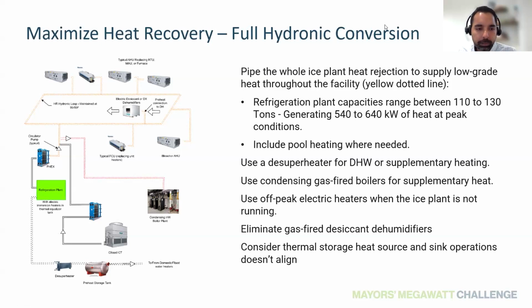Conceptually it's pretty simple: you have heat available from your ice plant that is generally being rejected to the outside through a cooling tower. When we try to decarbonize these buildings or facilities, we have a very good heat source available that we can use to supplement the existing heat in the building where it's actually needed - air handling units, dehumidifiers, AHUs, fan coil units, domestic hot water, floor water heating - anywhere you need hot water or energy that is currently being produced by the ice rink, you can leverage that and put it back into the building.